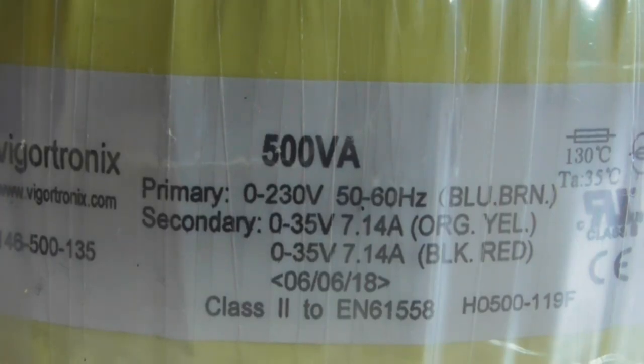This is the spec printed on the side of the Farnell transformer, and it says 500 VA. The secondary is 0-35, 0-35, and there it plainly shows 7.14 amps. If you do the mathematics, volts times amps, you get nearly 500 watts. So the specification of this, even though it's made in China, I would say was honest.